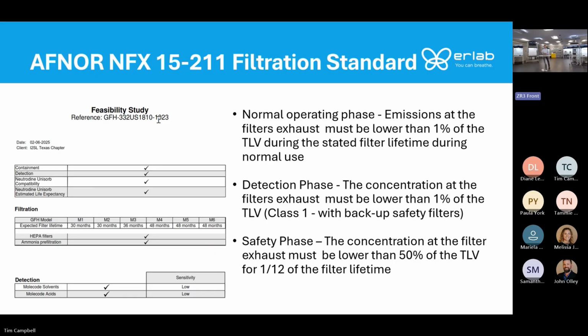And we do all that so then, like I said, you can get a filter lifetime in months. And during that stated filter lifetime, we're going to guarantee that no more than 1% of the threshold limit value of all those chemicals you're using in that hood would be detected past the exhaust of the carbon filters. So this is an example for our green fume hood. An M4, that's 4 modules of filtration, would be a 6-foot hood. This example from that chemical questionnaire I showed you before would be a 48-month filter lifetime. So if you use the hood how you said it would, we guarantee during those 48 months, no more than 1% of the threshold limit value would be detected past those backup filters.